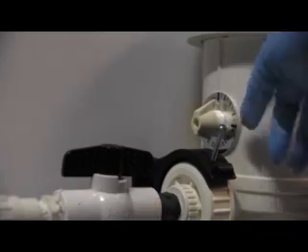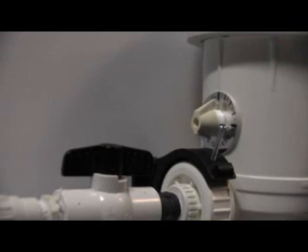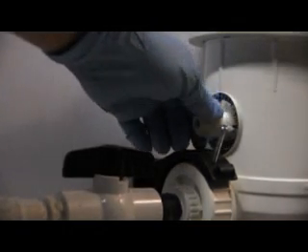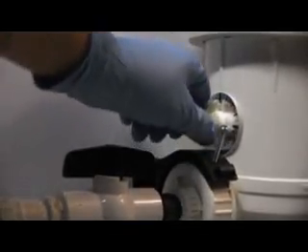So I've tested it extensively, and at 0, or close to 0, generally speaking, it's about 2 to 3 parts per million. So there's enough carryover and enough seepage in this system that I can assure you that you're not quite at off. There's always going to be some sort of a residual amount of chlorine coming through, but it's a very small amount and very difficult to detect at off. But I'm just telling you now, it's not completely off because I haven't seen it completely off, okay?